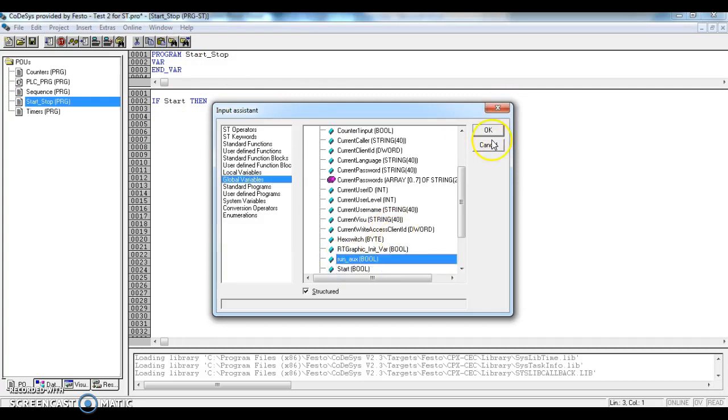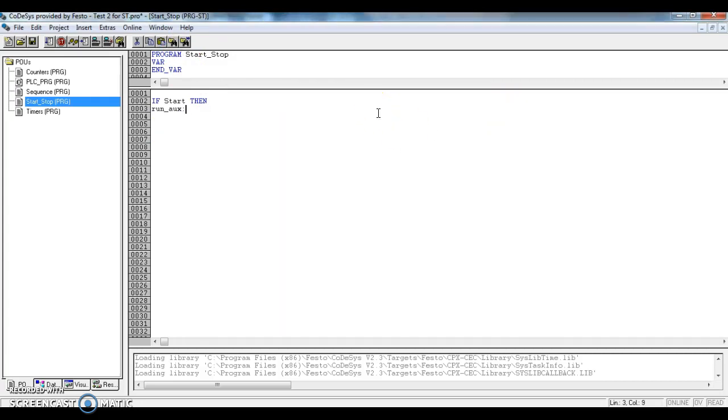A run auxiliary should go true. Now you will see in future videos what that means, but when I'm writing the sequence program, I will always check if the run auxiliary is true. Because if the run auxiliary is true, then the start button has been pressed and the stop button hasn't.